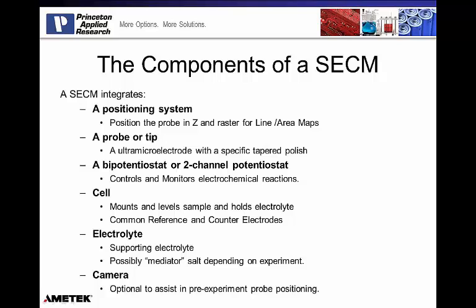Within the cell, since we're doing electrochemistry, it's typical 3-electrode type electrochemistry. We have a working electrode, but we often have two working electrodes, the sample and the probe. Then we're going to have a reference electrode and a counter electrode. And these can be common, meaning they can be shared between the probe and the sample itself, or they can be distinct, meaning that they can be separate working electrodes, reference electrodes and counter electrodes.